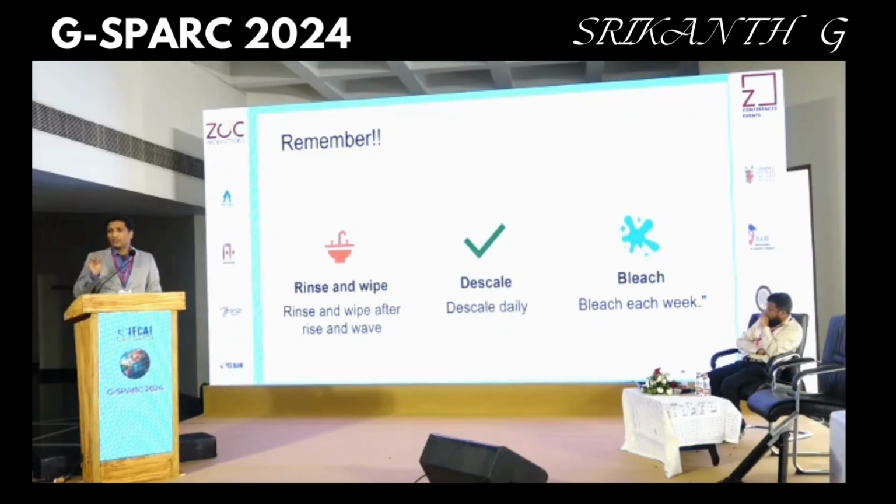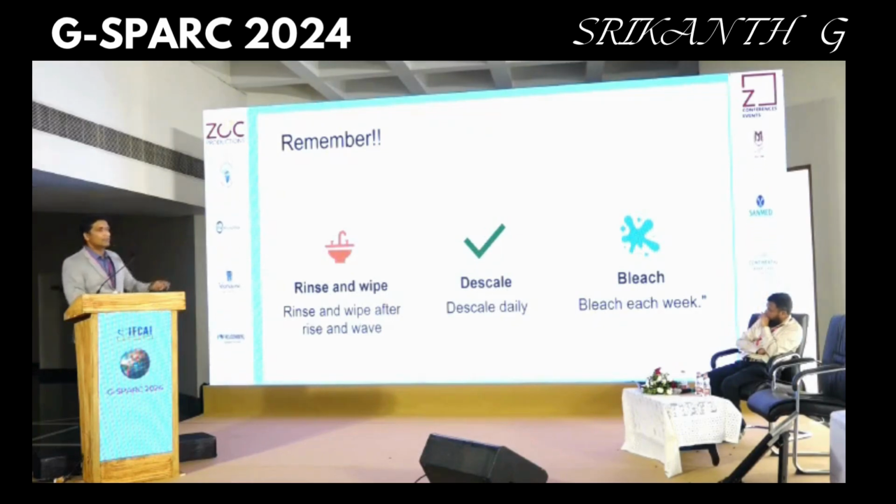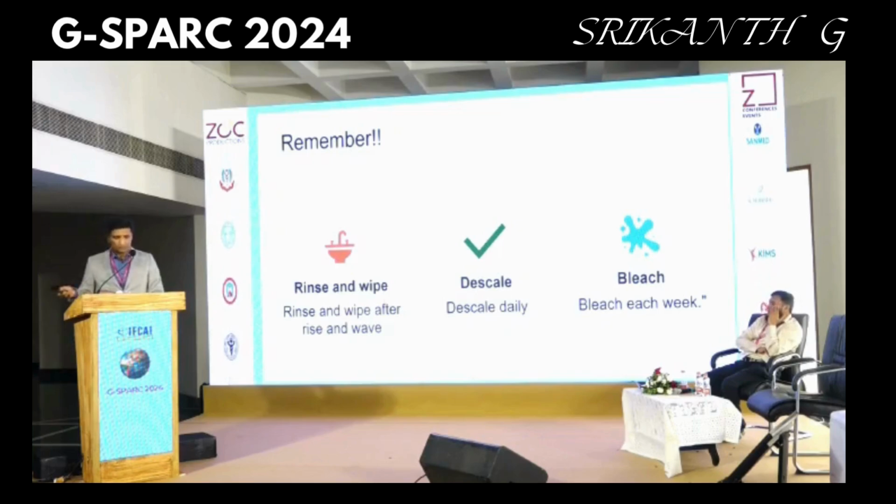Descaling is actually using citric acid to remove the scales that are formed in the internal hydraulics of the machine. That has to be done daily. And the third one is bleaching of the machine, again for the proper disinfection of the internal hydraulics. That has to be done by bleach.